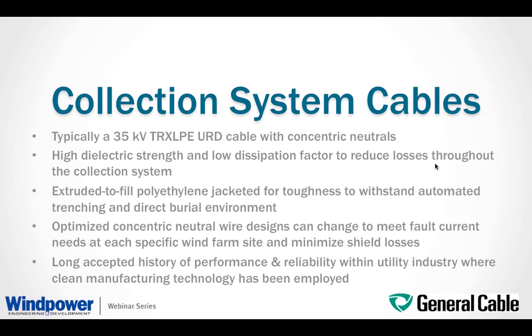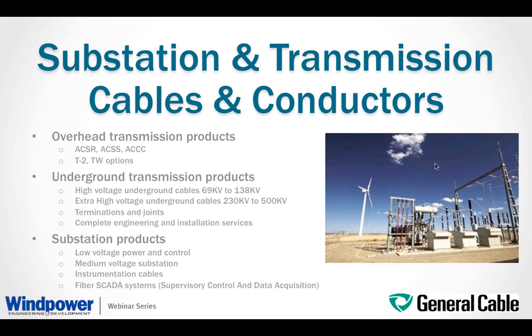For mechanical protection, an extruded tough polyethylene jacket is used to provide the toughness to withstand automated trenching and direct burial applications. The size of the concentric neutral is normally designed to meet the fault current needs at each specific wind farm project, and again to minimize the shield losses. Those designs have an accepted long history of performance and reliability within the utility industry, and have been adopted as the preferred design for the 35 kV cable portion of the collection system.